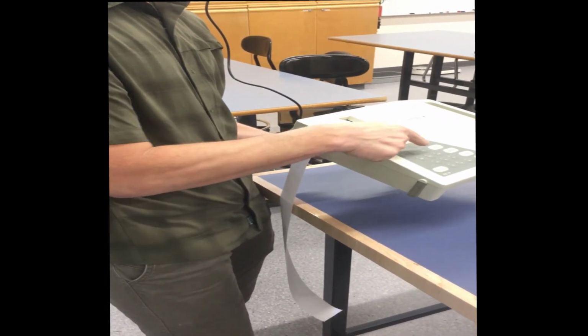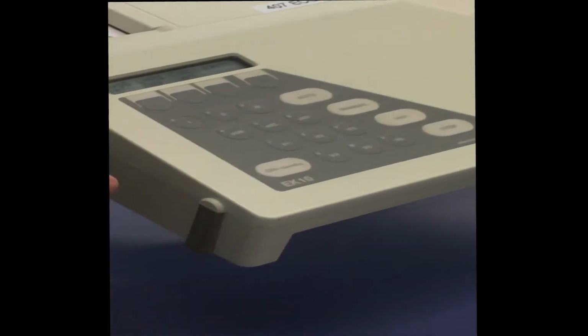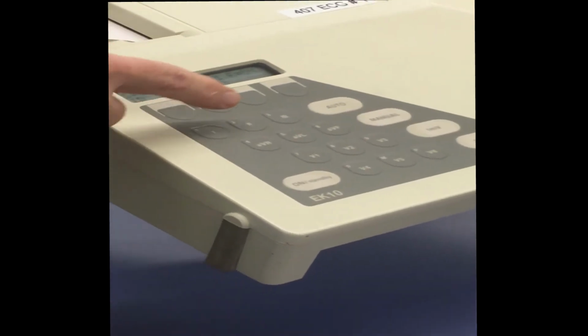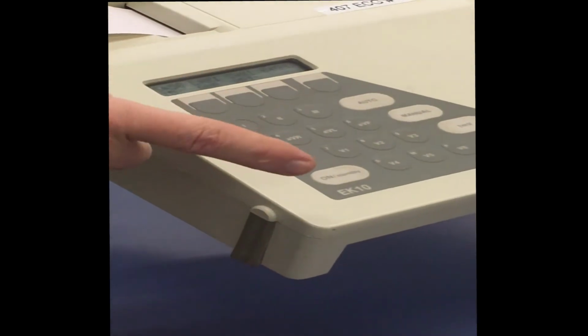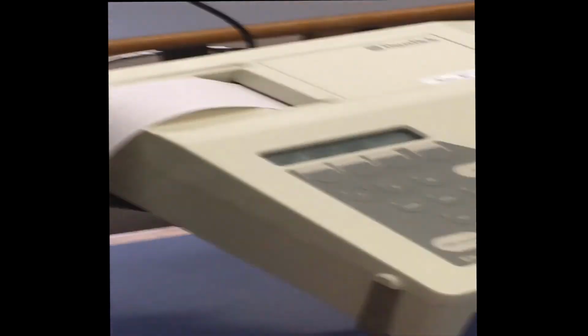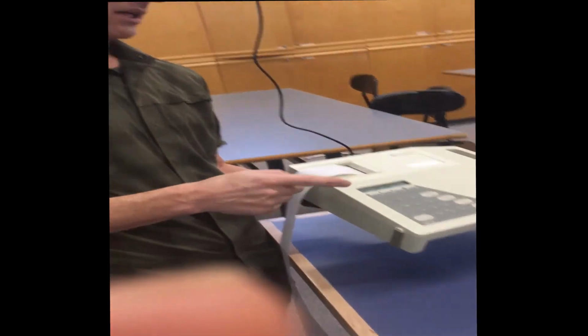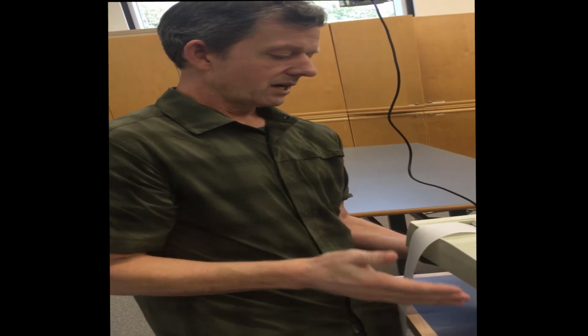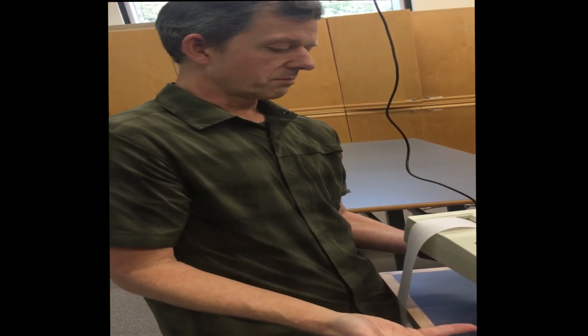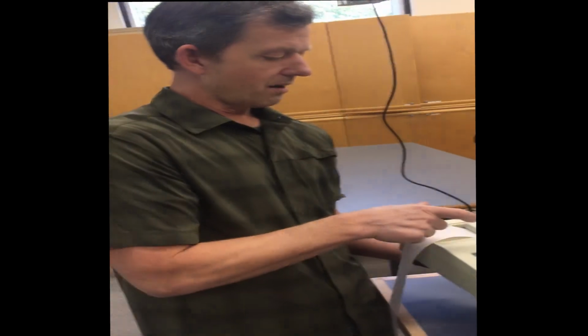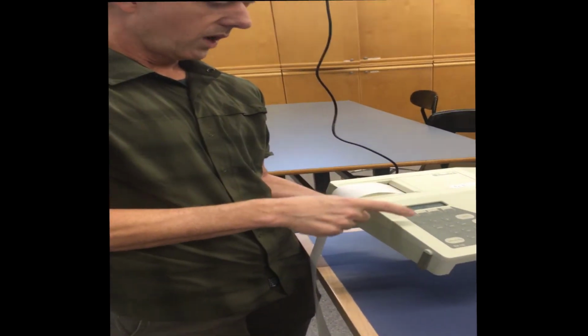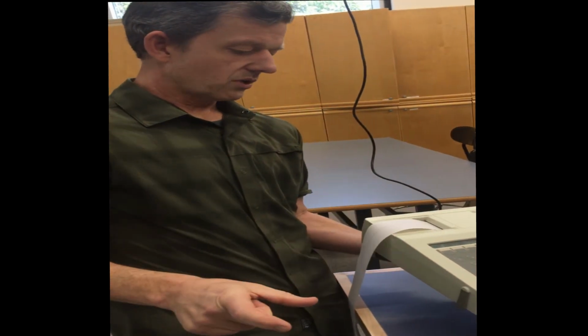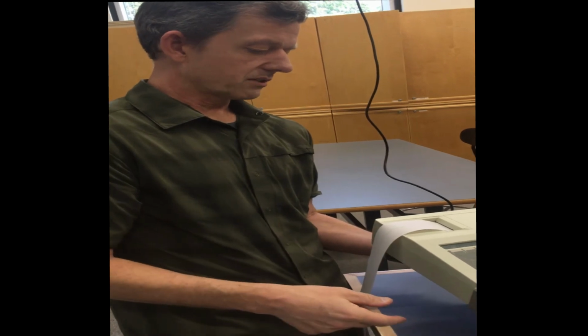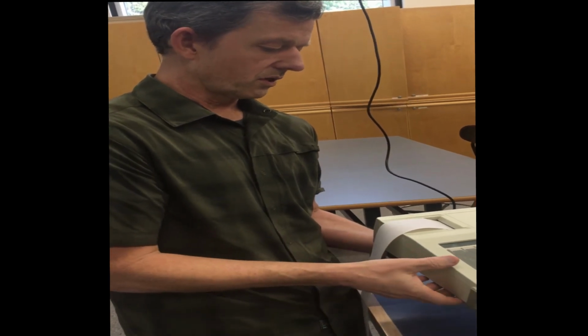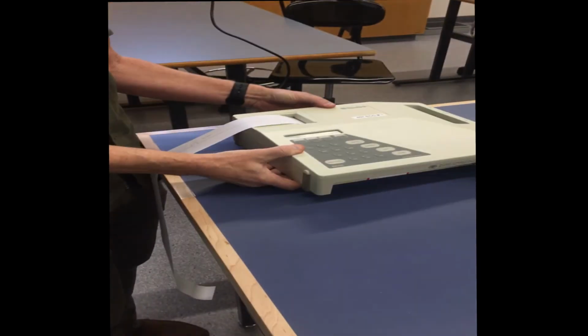The other button on the machine is auto, and what auto will do is it will sequentially go through the 12 different leads. So if you're doing a 12 lead ECG on a subject, you would press auto, and then it would automatically go through lead 1, lead 2, AVR, AVL, AVF. But for our purposes, we're going to use manual. We're going to press manual, have it run, then we're going to press lead 1, get a long enough strip, press lead 2, and go from there so that we sequentially go through all 12 of the leads. So that's pretty much it.